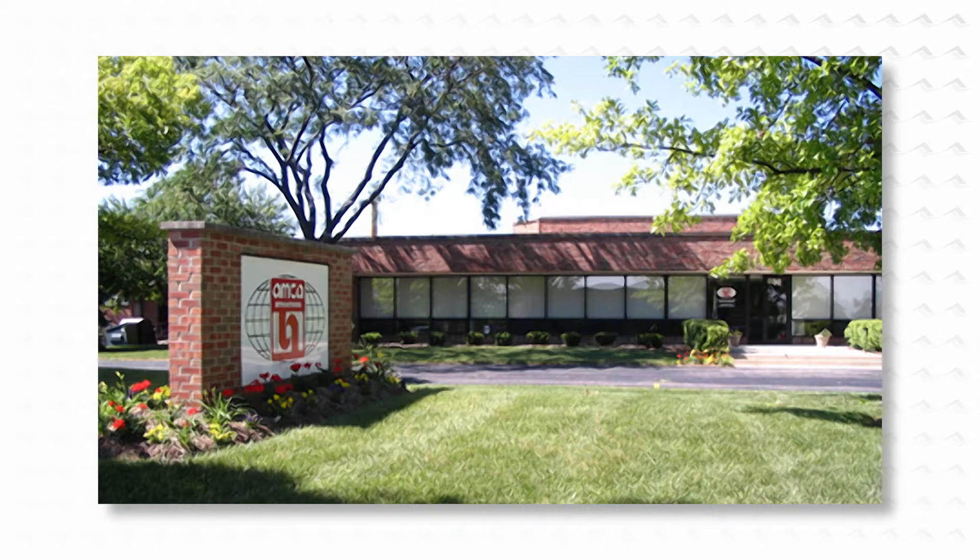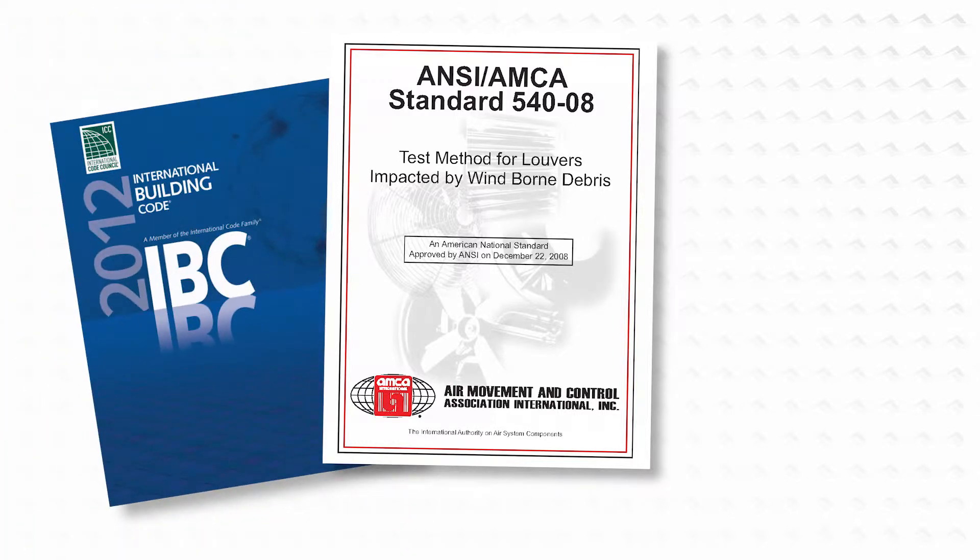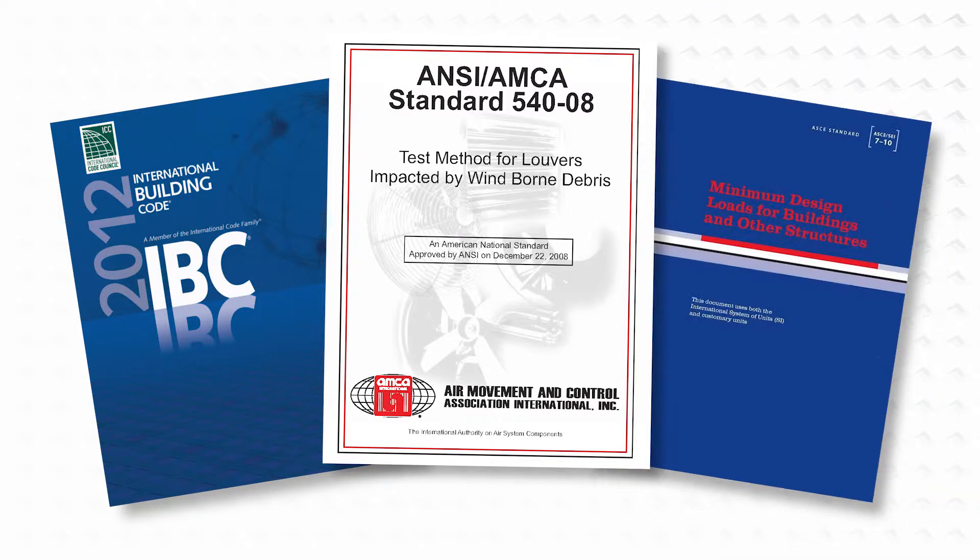The Air Movement and Control Association, or AMCA, recently introduced AMCA Standard 540 that requires large missile impact testing for louver products. The new AMCA Standard has subsequently been adopted by the 2012 International Building Code, or IBC, in accordance with the American Society of Civil Engineers, ASCE, 7-10, for certain types of buildings and structures located within the wind-borne debris region of the hurricane-prone region.